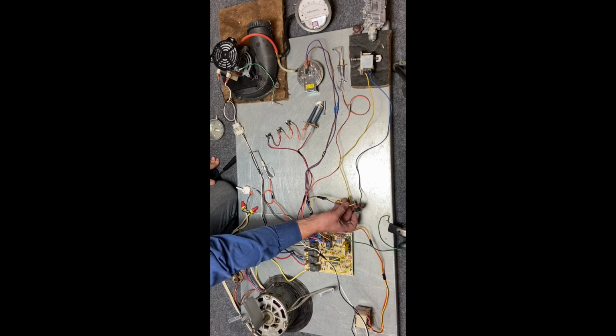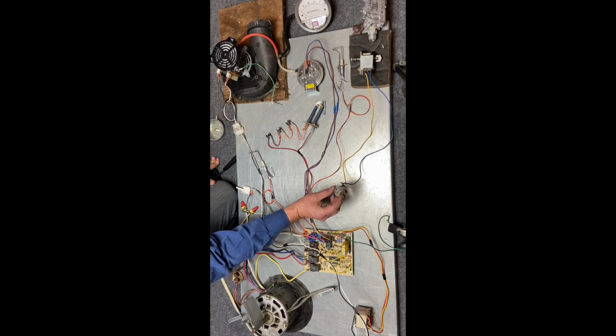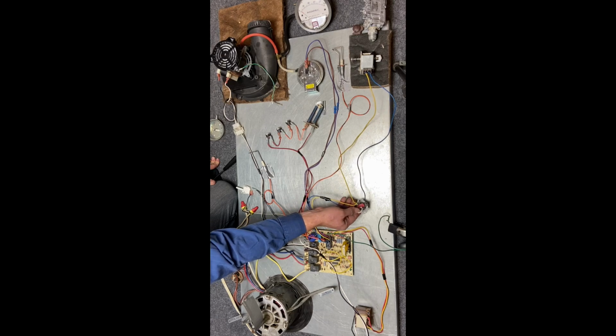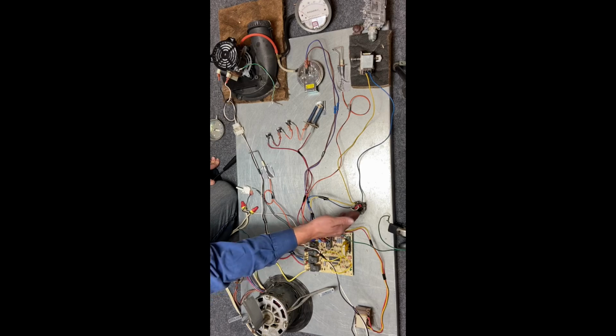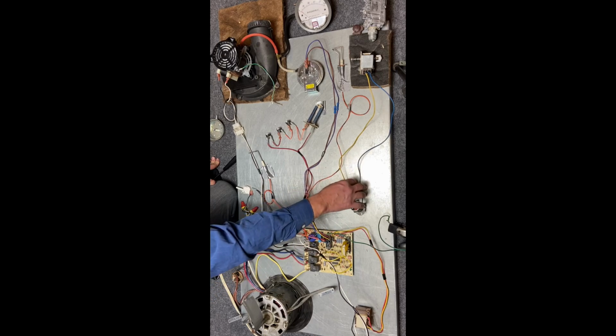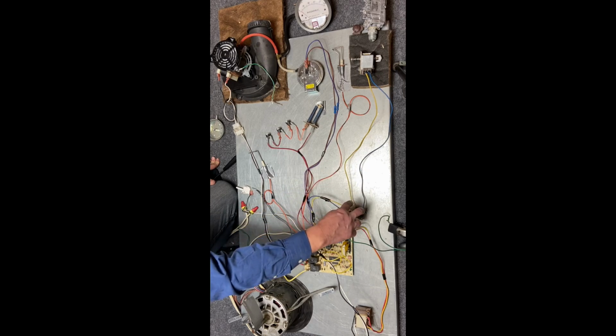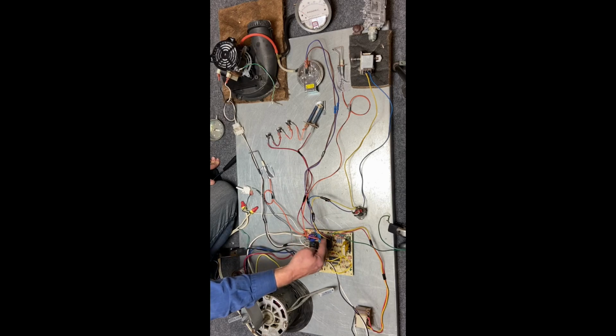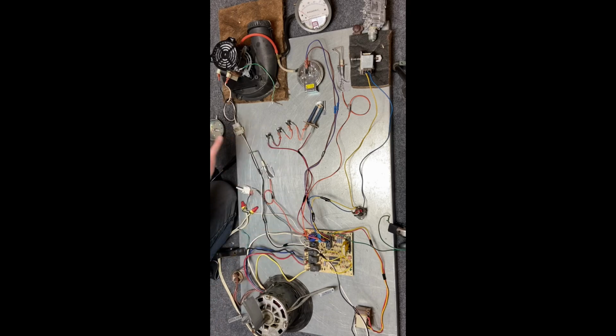This switch is also another safety switch. This particular switch is an auxiliary limit switch on the blower housing. So if this gets too hot, it actually breaks both of the wires to the switch. So 2 wires in, 2 wires back out to this multi-plug. So now we've gone through almost every single wire, and it's 2 wires, 2 wires, and 2 wires, except for here we have a single wire coming out of this plug.